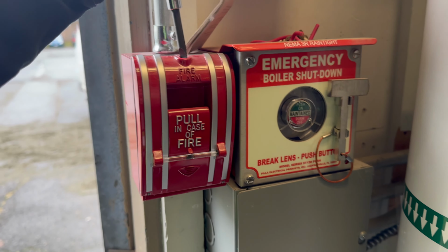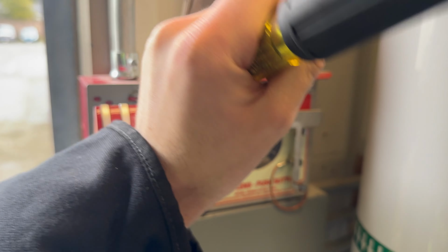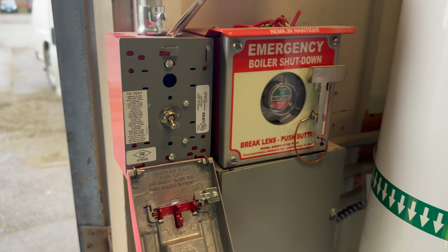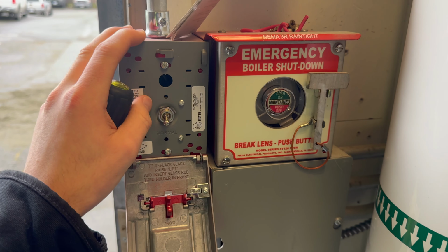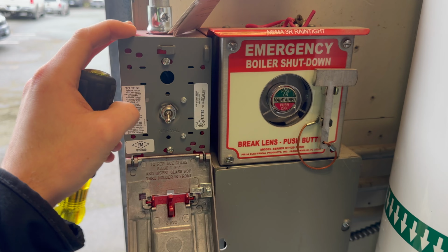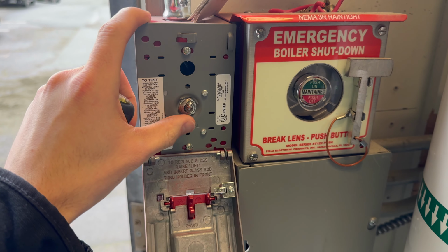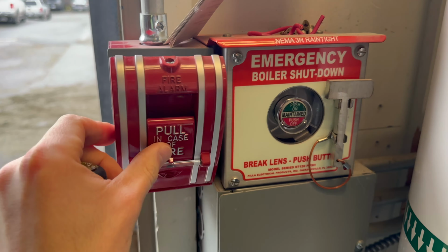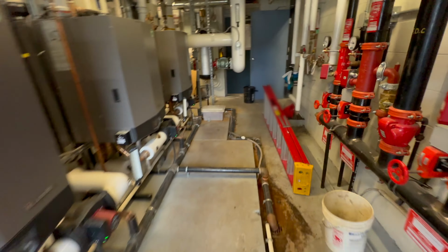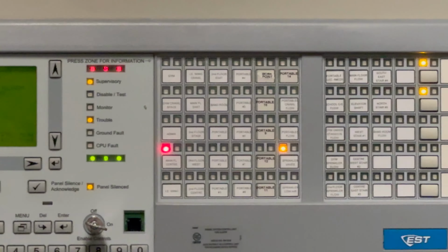Now lastly, we will do an alarm, but we're gonna still hit signal silence, just in the odd case the disables don't work properly. As I said, I've had that before, where the disables don't function and you'd rather just hit signal silence anyways, just to make sure your bells aren't gonna be going off until the system's reset. Like, it takes 1 second to hit it. In the odd chance it doesn't work, it's definitely worthwhile doing. Did you receive an alarm? Our main floor center.